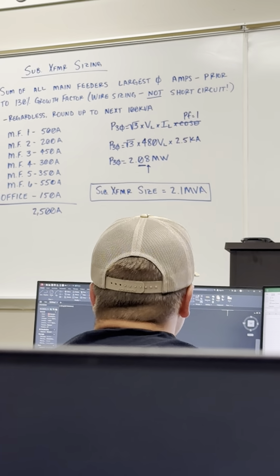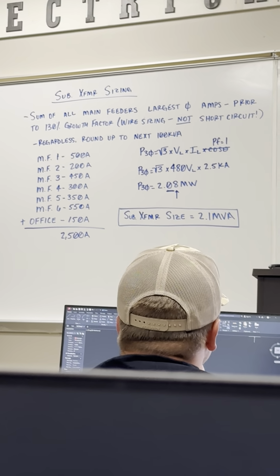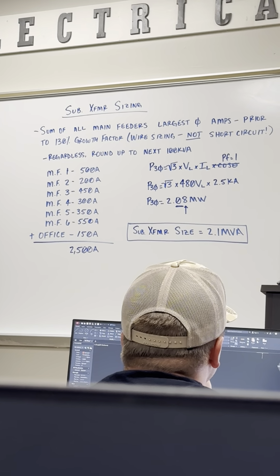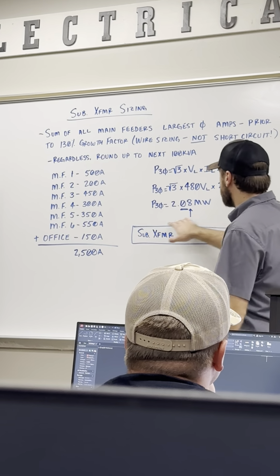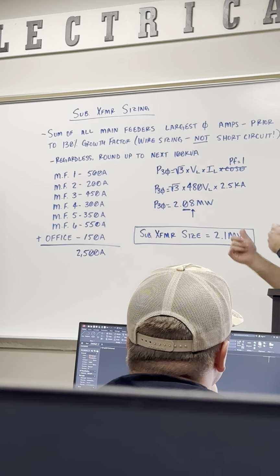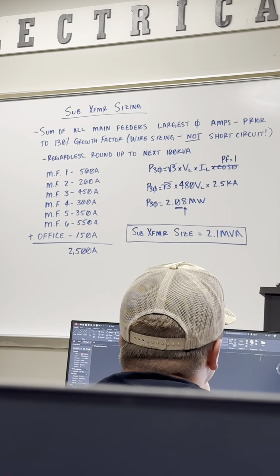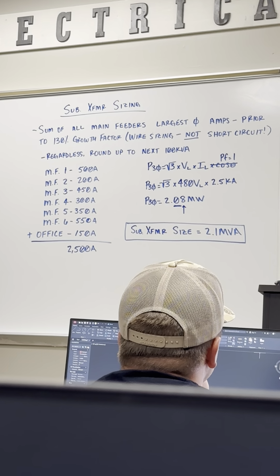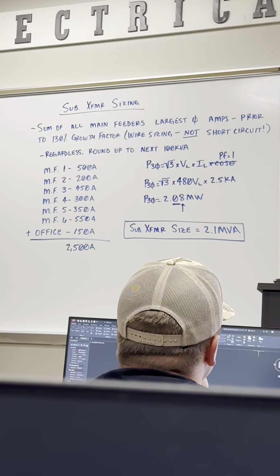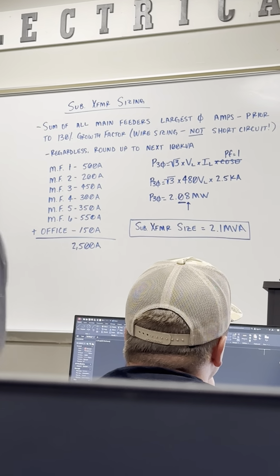So like I said, there's not a set list of substation transformer sizes. It's all based on what we calculate right here. We're going to round up to that next 100 kVA, and that's going to be our transformer size. That's what we're going to kind of custom order, so to speak.